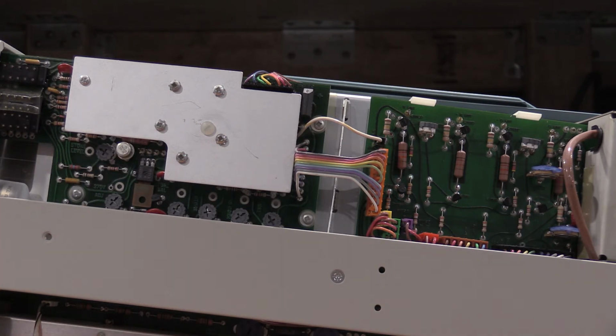So the way these measurements are taken is the 370 volt supply is referenced to ground. Everything else is referenced to flood gun cathodes, which is pin 3. So I will get the meter set up and we'll do those adjustments here real quick. I did take the adjustments down from the other D1 that I have that's working correctly.